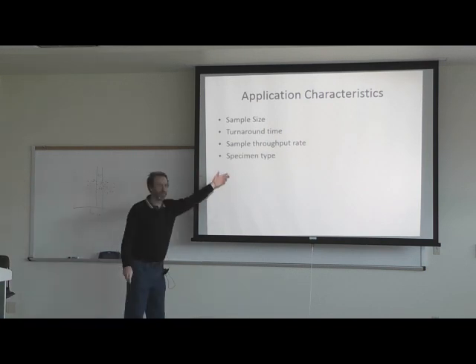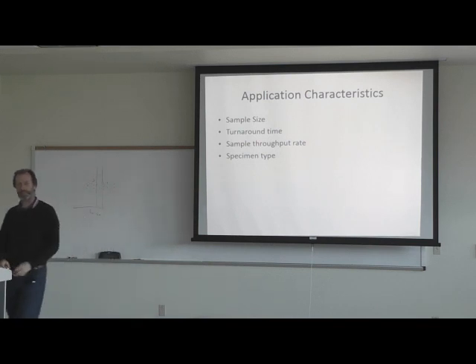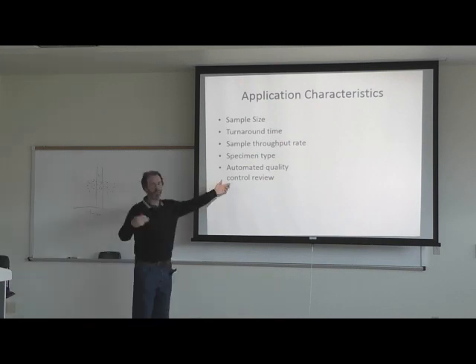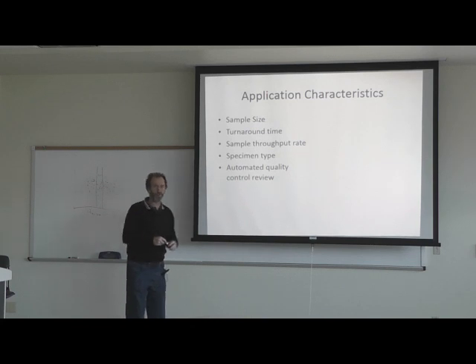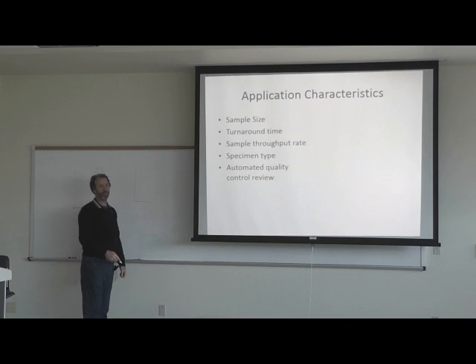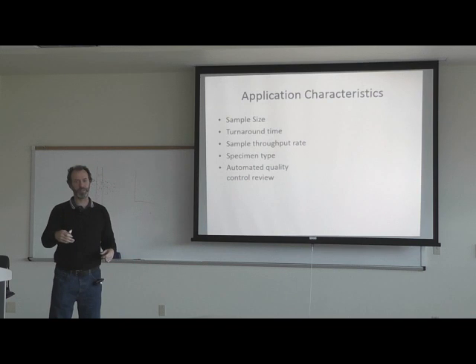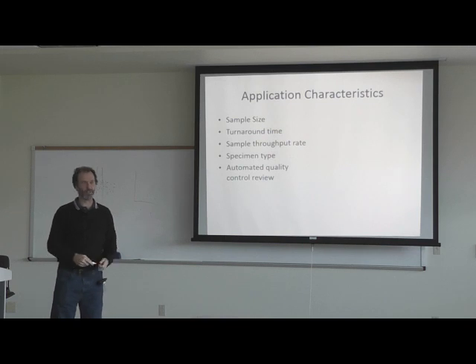You've also got to know what the specimen type is — serum, plasma, CSF, etc. A lot of these new methods have automated quality control. Rather than writing out Levey-Jennings charts manually, the computer that runs the machine keeps a Levey-Jennings chart in its file. When it fails Westgard rules, it will flag you — for example, a 1-3S rule violation, 2-2S, or R-4S.